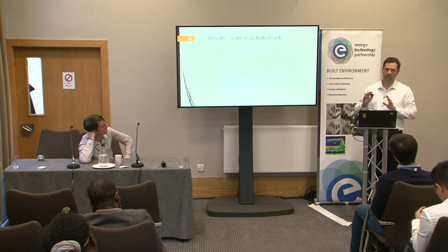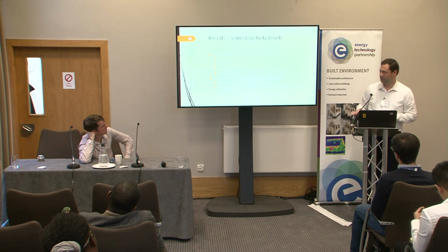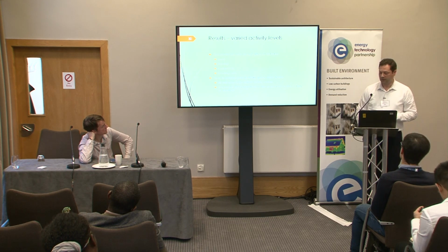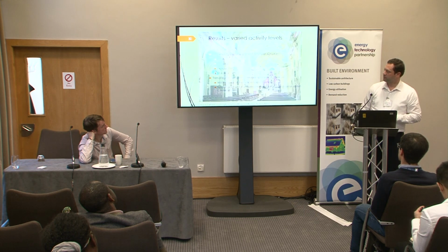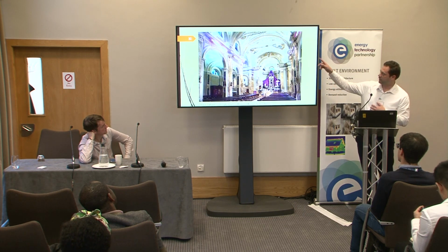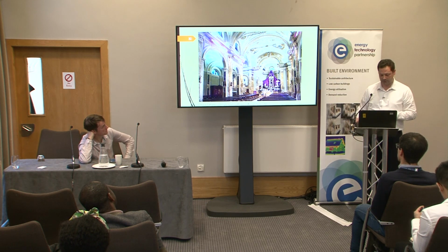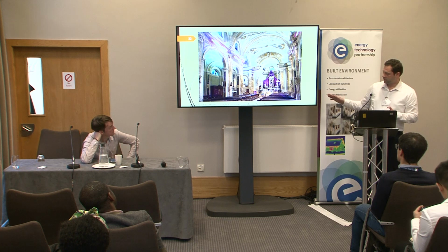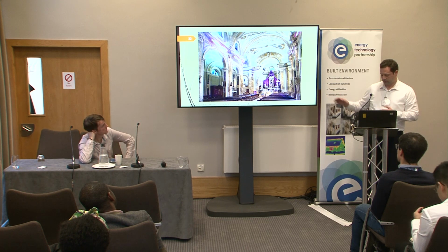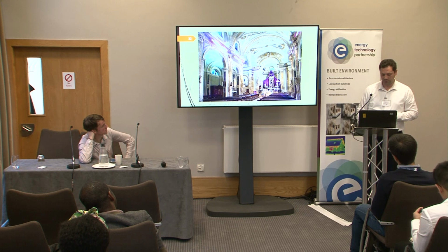There has been a tendency for churches to think we must have underfloor heating, but very old historic churches, hundreds of years old, tend to have graves and flagstones with inscriptions on the floor, so we're not going to be able to rip up these floors and install underfloor heating, and it's often not that successful in large volume buildings because you're still trying to heat the building fabric to a uniform temperature. So if you take the pews out, this has got high temperature radiant panels that work at around 1,000 degrees. That covers quite a large floor space, and you could do a different activity there if the pews were not there.